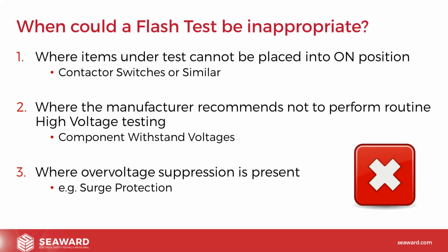However, there are times where it may not be appropriate to perform a flash test. The flash test can only prove to a certain point. And some of the considerations we have to think about when performing these sort of tests are on screen now. So firstly, in order to test the unit properly, we have to make sure any switches are in the on position. Otherwise, we may only be testing up to the point of the switch.